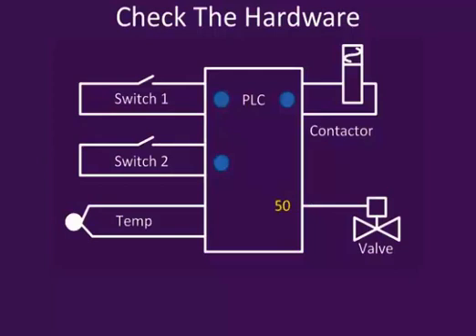It's essential that you do this because that proves that there isn't a bias, an incorrect voltage floating around in there, and that they are both working on the same 0-volt reference. Finally, you force it back to 0, you check the valve goes back to 0, and then you remove the force. It's very important to remove the force so that the thing is back on auto control.